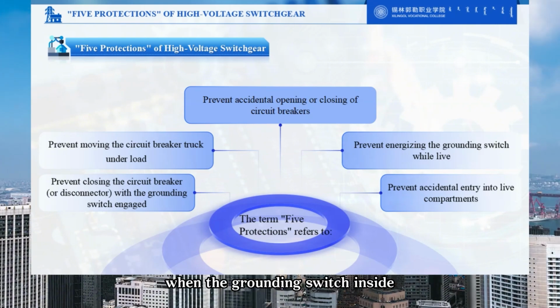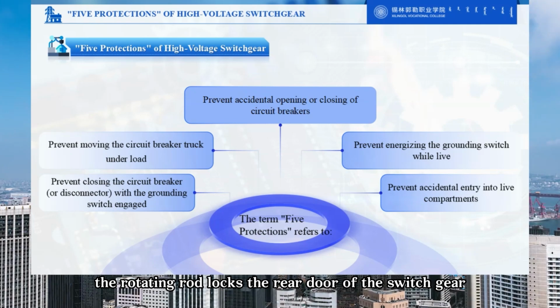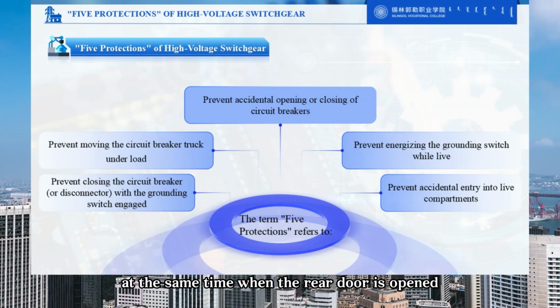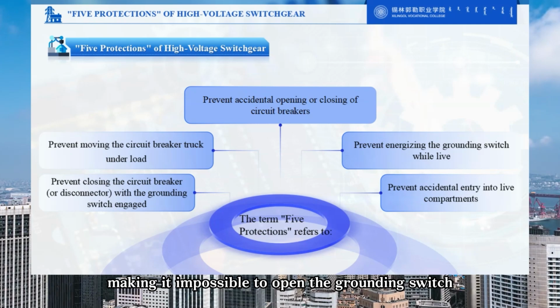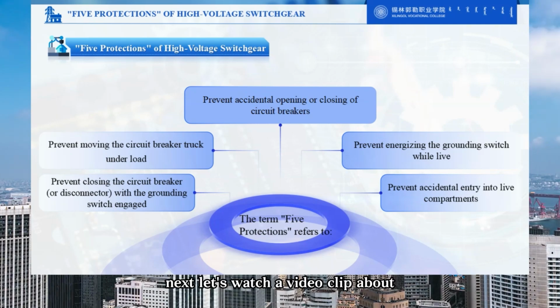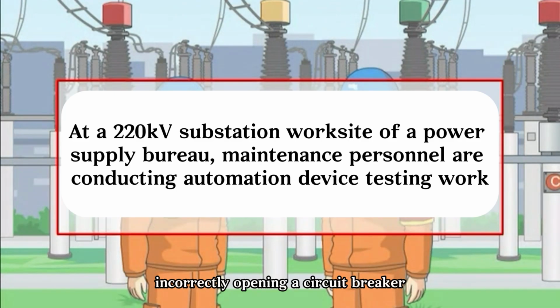When the grounding switch inside the high voltage switchgear is open, the rotating rod locks the rear door of the switchgear, preventing the rear door from being opened. At the same time, when the rear door is opened, the grounding switch rotating rod is locked, making it impossible to open the grounding switch. Next, let's watch a video clip about incorrectly opening a circuit breaker.